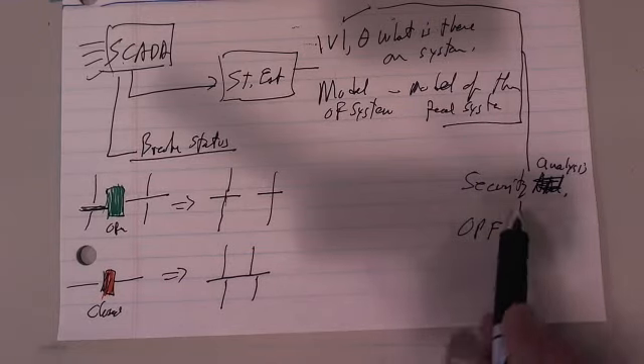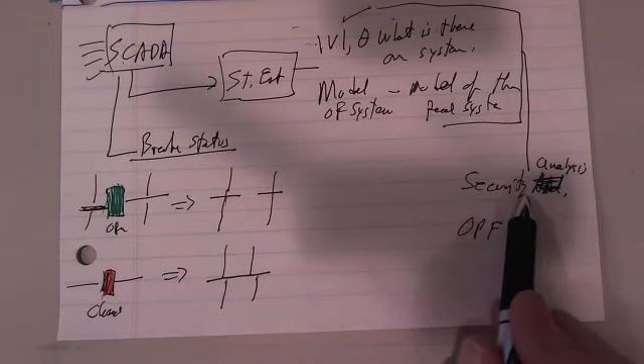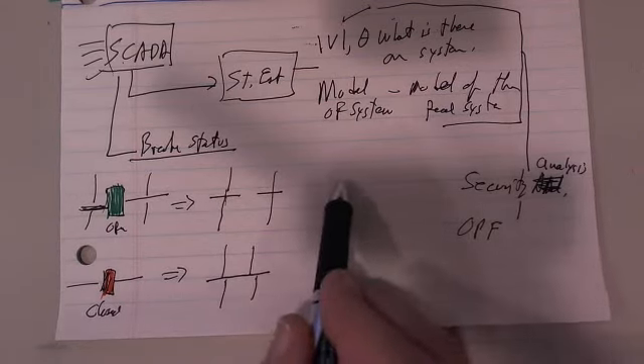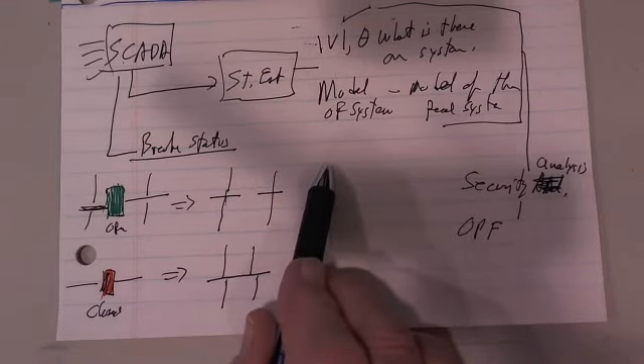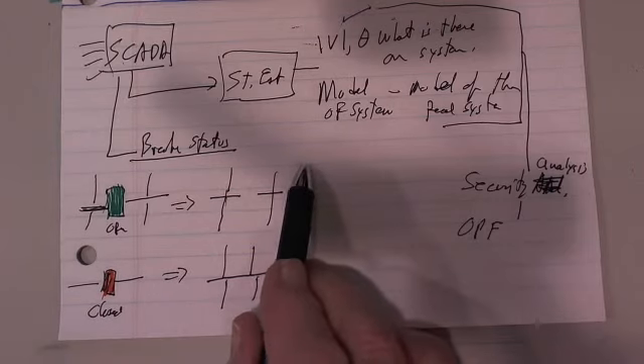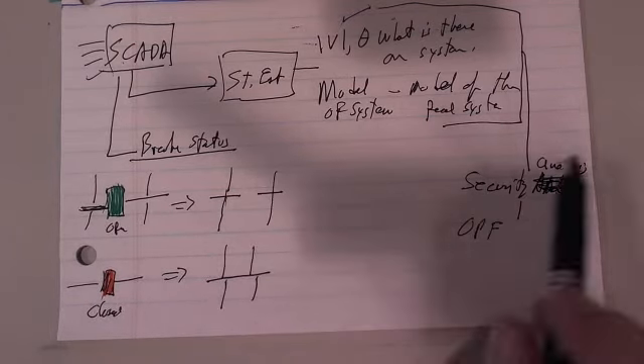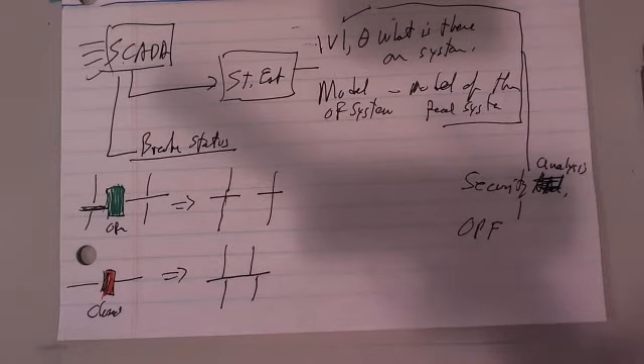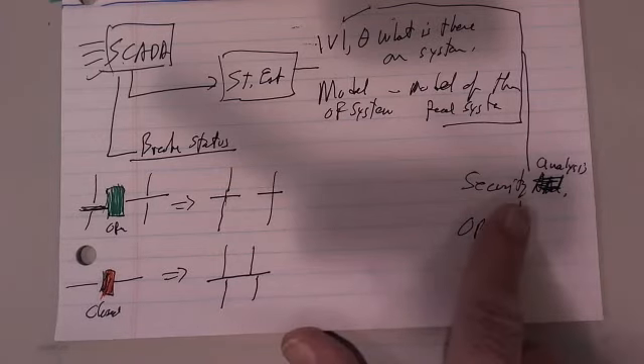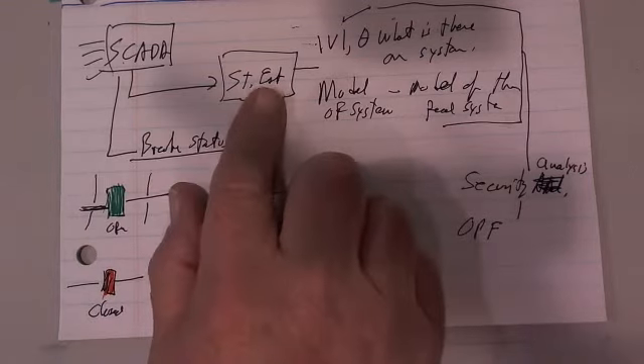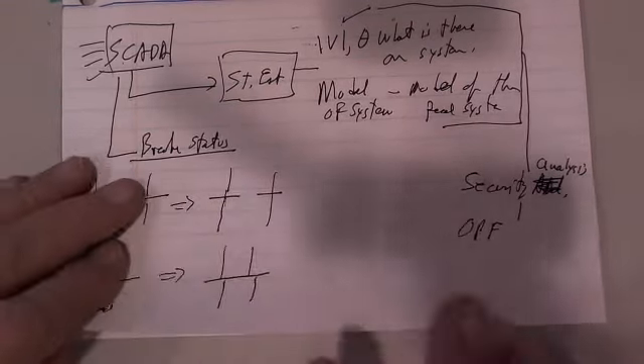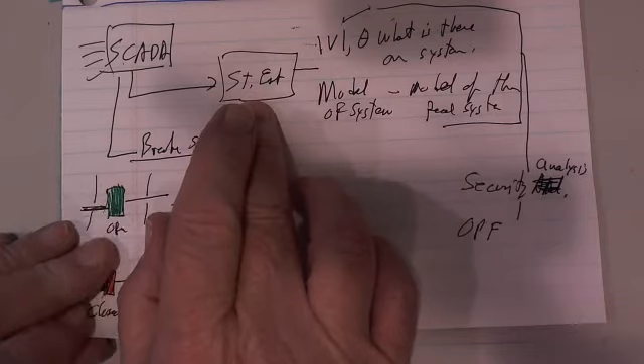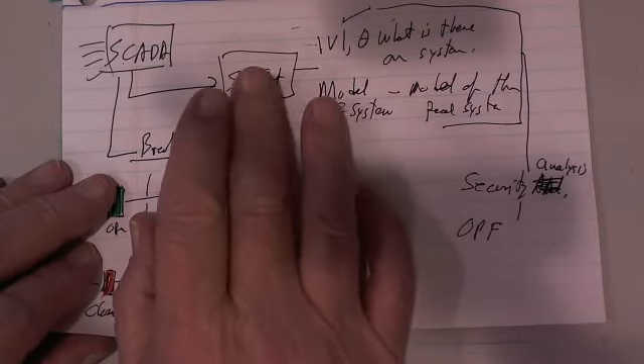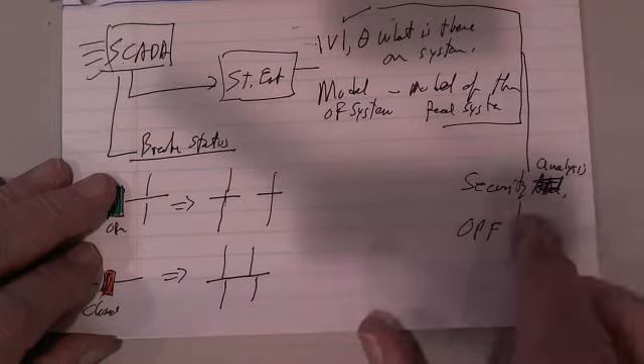If security analysis says you've got a problem over here, there should be a way of going out to the power system and correcting something. For example, as we'll see later, going out and changing the dispatch so we change the transactions and power flowing across the system will get rid of that security problem. So that's what the state estimator is basically all about: bad data detection and identification, estimating quantities we don't actually measure, and using it to initialize our model for security analysis.